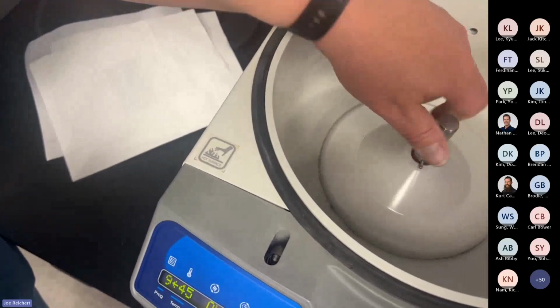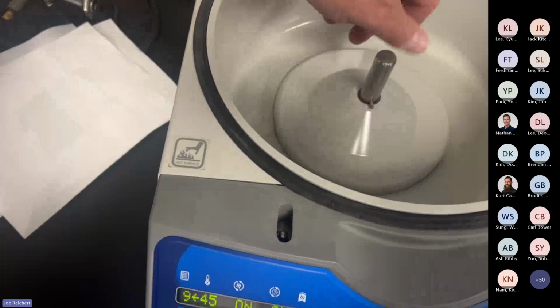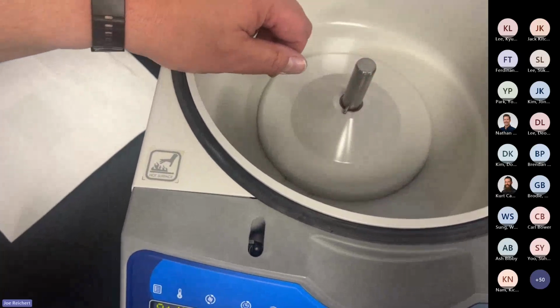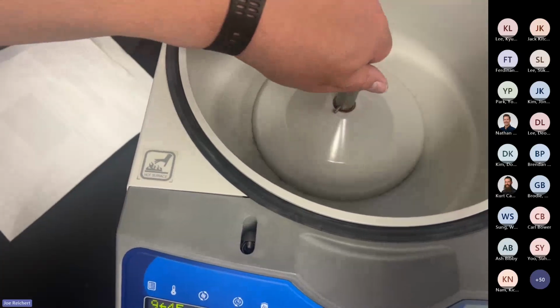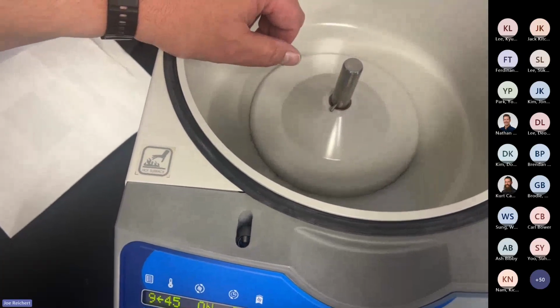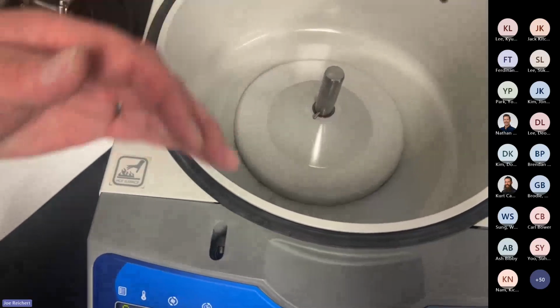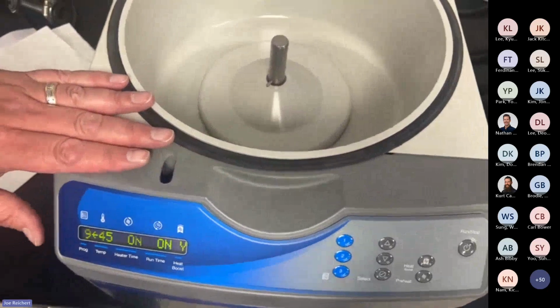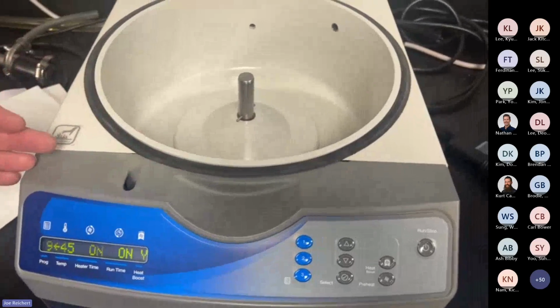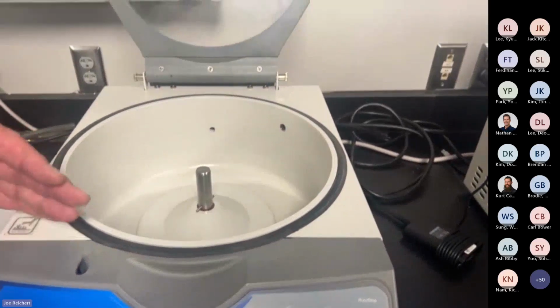You don't have to have the unit on or running or spinning or anything to know that's going to do that. Just open the lid, slight little turn of that shaft, and you can see it move. It should be just as simple as that. Should move very easily. But if it doesn't retract back, this unit uses a solenoid to pull the latch back. But whenever you hit run for it to go forward, you can hear the cooling fan on when you're in front of the machines. But as soon as you turn that rotor or turn that shaft just a little bit, you'll hear the cooling fan stop.